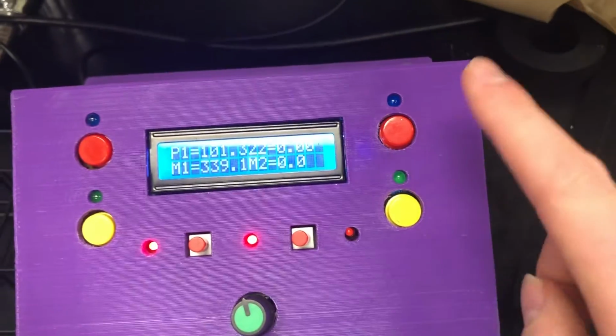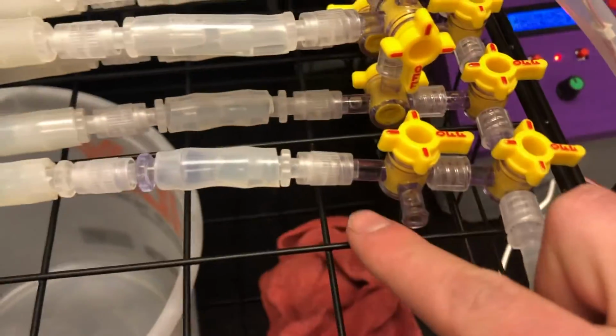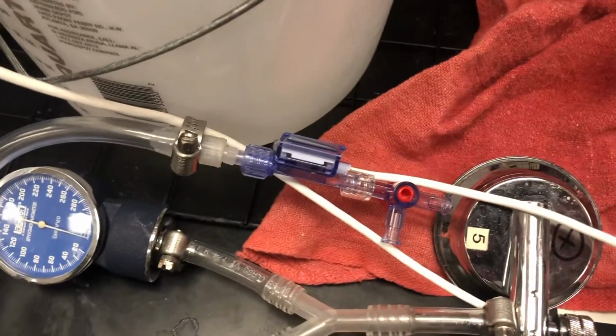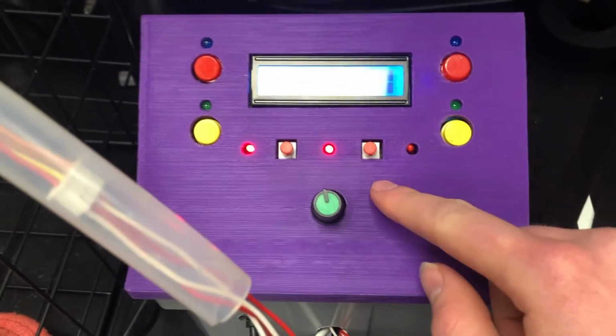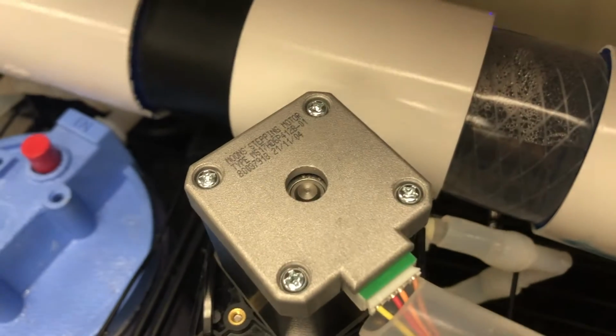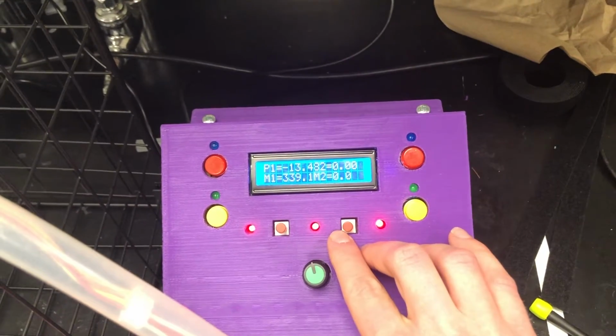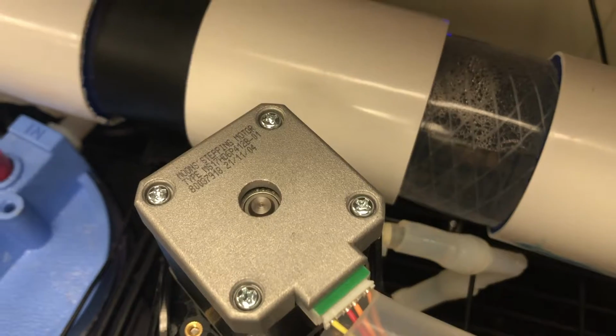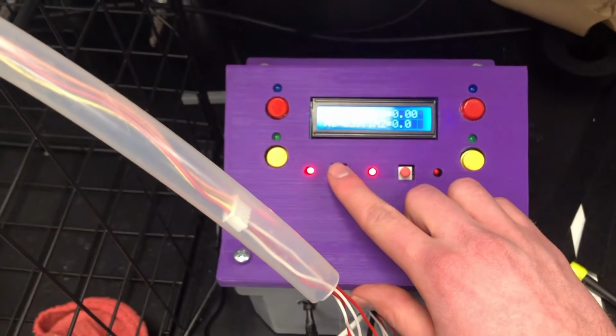And then this side does the same thing, except for the second pressure transducer. So this pressure transducer is controlled by this set of buttons over here, and the pressure transducer that normally goes right over here, which is connected to this sphygmomanometer, is controlled by these buttons right here. This button right here completely stops the pump. As you can see, it's going back on now. And this button right here reverses the direction of the pump.